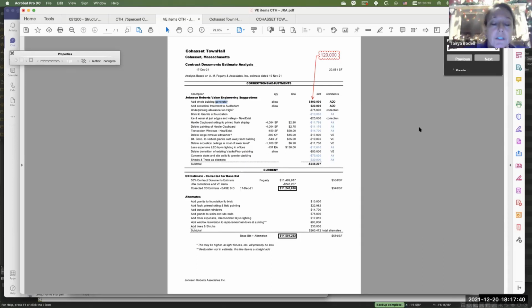You could run it above essential services, below total load, and just shut down empty spaces if needed. Or the other option is we could have one of the pieces of rotating generation at the Town Hall contributing to the grid when it's operating, and if the microgrid goes down, powering the Town Hall to give it perfect power.